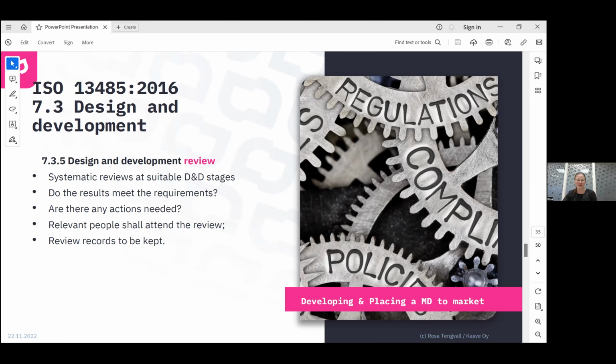Reviews, also from the MDR. You need to have systematic reviews at suitable stages of the design and development. Basically reviewing if the outputs meet the inputs. Do you have the results so that they meet the requirements? Are there any actions needed? Are relevant people attending the review? Meaning that you need to have not only the technical expertise, but also clinical expertise, so that you ensure all the way that the product you're developing is also fulfilling the intended purpose, fulfilling the medical part of where you want it to be used. And you will have records from these.